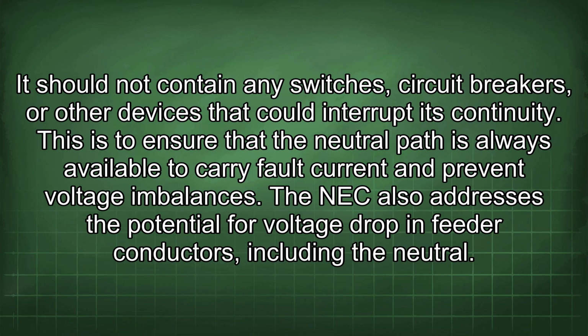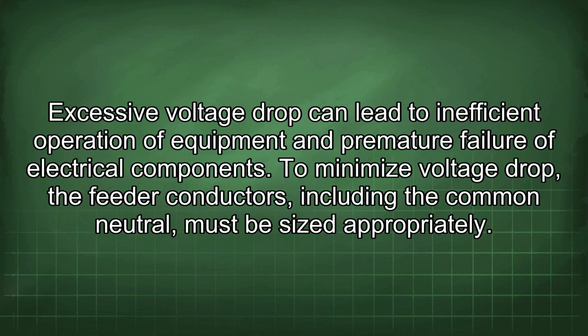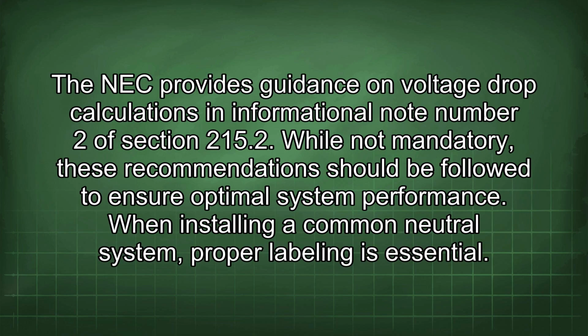The NEC also addresses the potential for voltage drop in feeder conductors, including the neutral. Excessive voltage drop can lead to inefficient operation of equipment and premature failure of electrical components. To minimize voltage drop, the feeder conductors, including the common neutral, must be sized appropriately. The NEC provides guidance on voltage drop calculations in Informational Note number 2 of Section 215.2. While not mandatory, these recommendations should be followed to ensure optimal system performance.